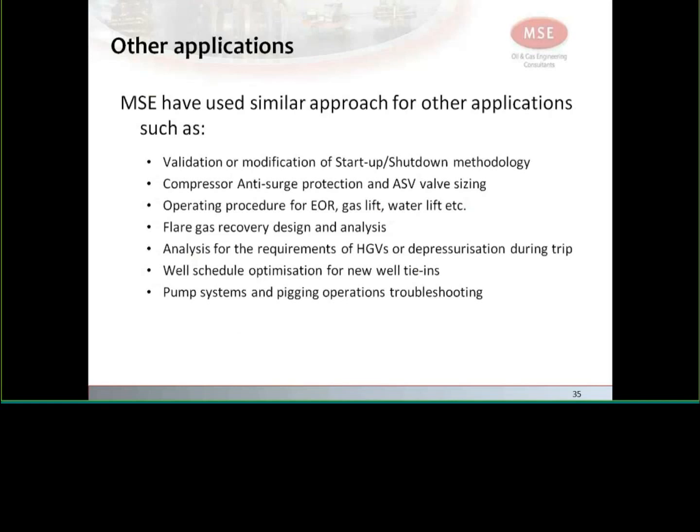We also applied the same methodology for a flare gas recovery system for the compressor, with very good results as well. And similarly for pump systems, because we work not only with compressors but also pump systems, we were able to do some very valuable troubleshooting involving the recycle valve sizing, wear, replacement, etc.